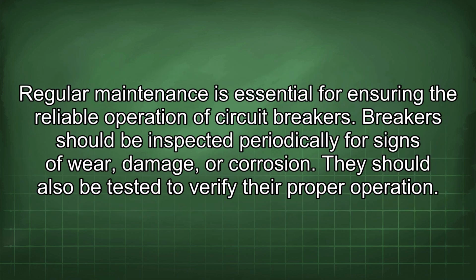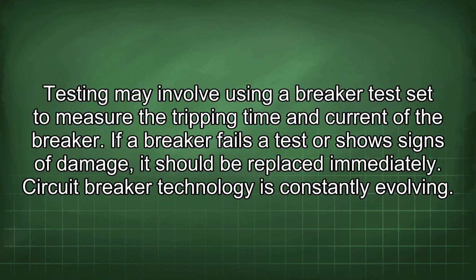Regular maintenance is essential for ensuring the reliable operation of circuit breakers. Breakers should be inspected periodically for signs of wear, damage, or corrosion. They should also be tested to verify their proper operation. Testing may involve using a breaker test set to measure the tripping time and current of the breaker. If a breaker fails a test or shows signs of damage, it should be replaced immediately.